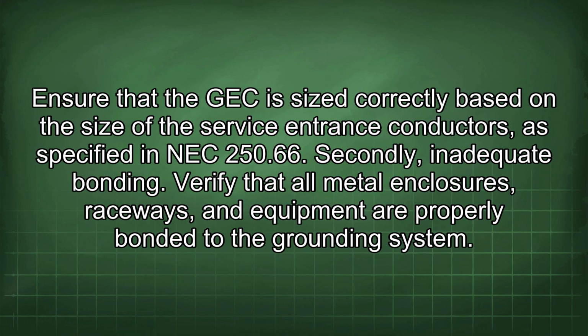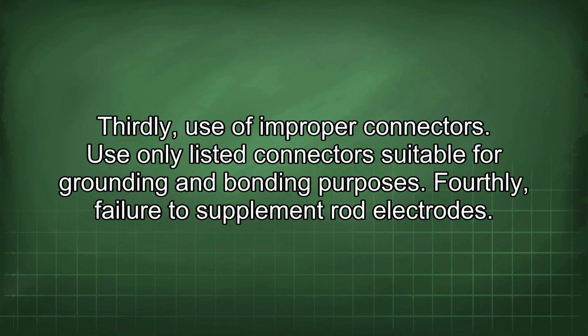Ensure that the GEC is sized correctly based on the size of the service entrance conductors, as specified in NEC 250.66. Secondly, inadequate bonding. Verify that all metal enclosures, raceways, and equipment are properly bonded to the grounding system. Thirdly, use of improper connectors. Use only listed connectors suitable for grounding and bonding purposes.